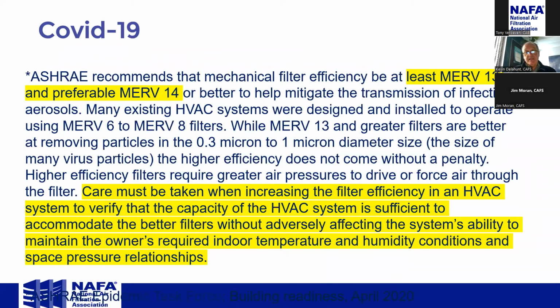Because of the ASHRAE Epidemic Task Force coming out with suggestions of MERV 13 and preferably MERV 14, I would think that future versions of ASHRAE Standard 62 will also reflect that and have at least MERV 13, if not MERV 14 in their systems, which will hopefully change some of the design parameters that will be required when you go from a MERV 8 to a MERV 13 or 14. And they also put in that care must be taken when increasing the filter efficiency in an HVAC system to verify the capacity of the HVAC system is sufficient to accommodate better filters without adversely affecting the system's ability to maintain the owner's required temperature, humidity, and airflow.